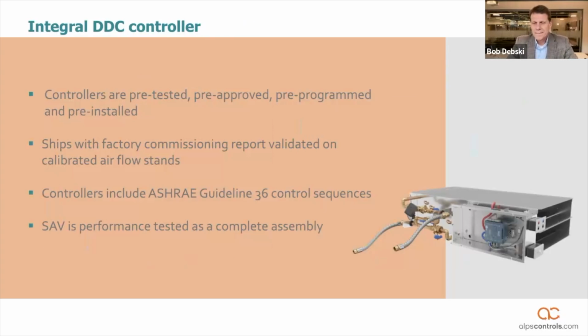So, integral DDC controller. This is important to understand. The smart air valve cannot exist without that DDC controller. As mentioned, all of that intelligence is contained within the controller. So this creates an opportunity. Now, all of a sudden, if you're providing the controller, you get to provide the smart air valve. It's an integral assembly. It's very important to understand that. It's also important to understand that these assemblies are tested totally at the factory. Unlike a lot of conventional VAV boxes that are tested in the field, this does not leave until it's confirmed that it's controlling accurately and precisely. This is an important feature that we're going to see here very shortly, what kind of impact that can have on schedules.